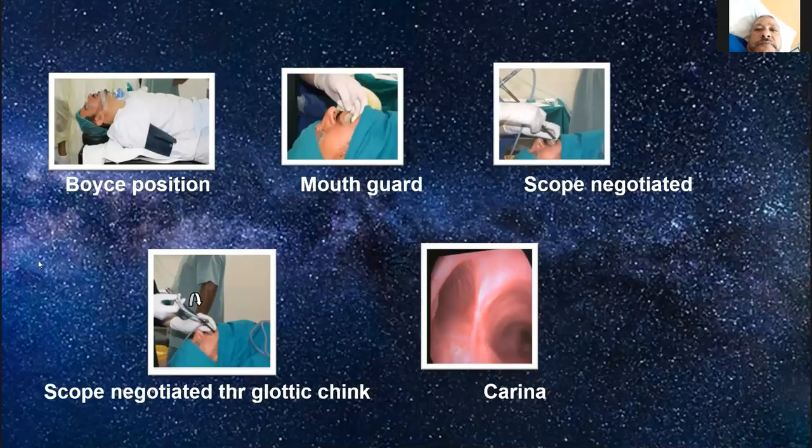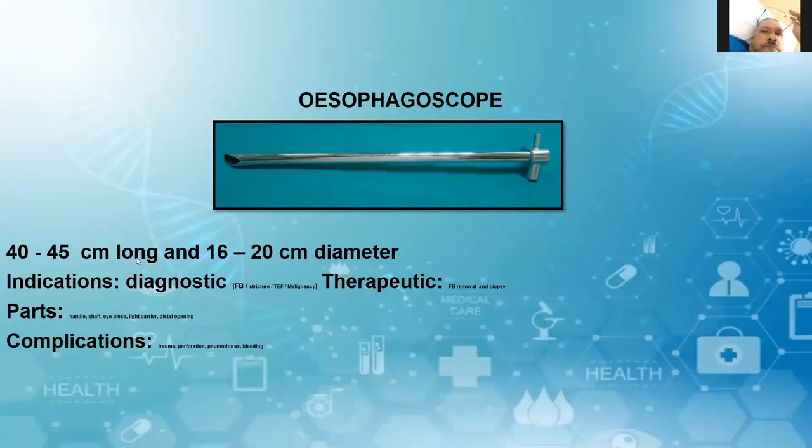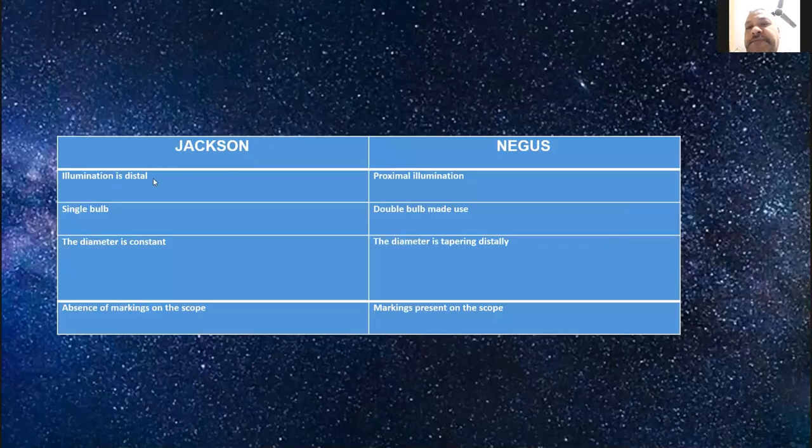Oesophagoscopes: normal length is 40 to 45 cm, diameter 16 to 20 mm. You should know the indications, both diagnostic and therapeutic. The parts are: handle, shaft, eyepiece, light carrier, and distal opening. Jackson scope versus Negus scope: in Jackson scope, illumination is distal with a single bulb, and the diameter is constant. In Negus scope, the diameter tapers distally, it has double source of illumination, and markings are present on the endoscope.